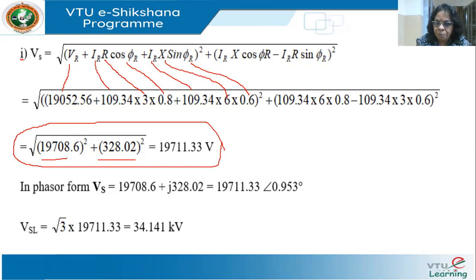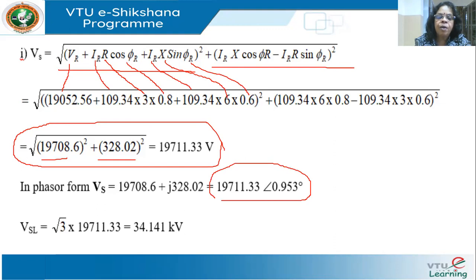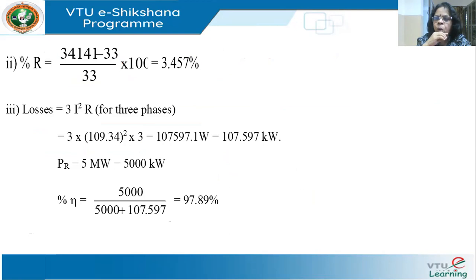Writing in phasor form: VS = 19,708.6 + j328.02 V, which gives a magnitude of 19,711.33 V at an angle of 0.953°. This is the line-to-neutral voltage. Multiplying by √3 gives the line voltage VS(line) = 34.141 kV. The angle does not get multiplied by √3 — only the magnitude does. The percentage voltage regulation is (34.141 − 33) / 33 × 100 = 3.457%, higher than in the previous example because the power level is greater, leading to more current and more voltage drop.